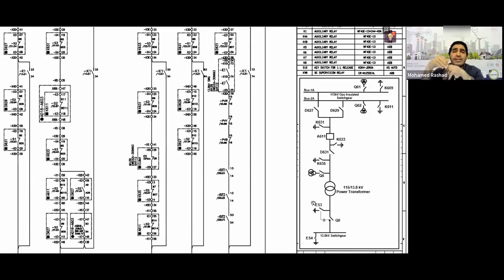The breaker on the other side doesn't have a disconnector switch because the breaker was originally small in size, right? So we said this breaker could be made withdrawable, meaning before the pull, right? Am I wrong? When I came to the high voltage, I found the breaker was large in size and I couldn't make it withdrawable. What did I do?